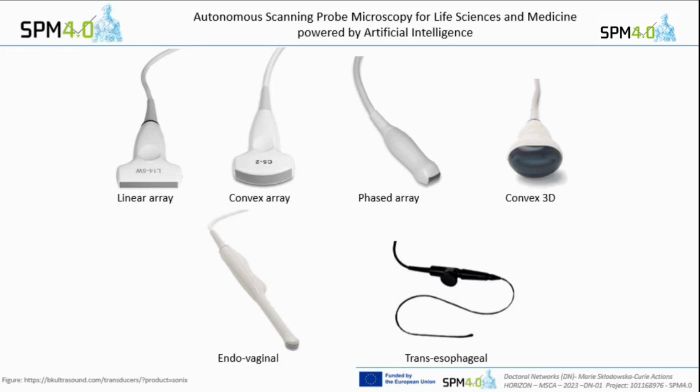So there is not only a single piezo element. Here are about 120, 200 elements included, and you don't use all of them together. You use only a part.